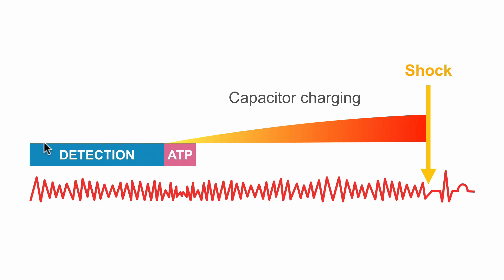If you think about the arrhythmia, we have a detection time delay where the arrhythmia has to be sustained long enough for the device to consider therapy. If detection is met and the device decides to charge for a shock, we have further time before therapy is eventually delivered. It's not something we get overly concerned about, but it's worth being mindful that after detecting the arrhythmia there will be a delay until the high voltage shock is delivered whilst the capacitor charges.